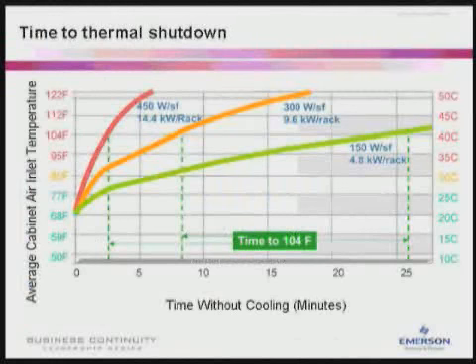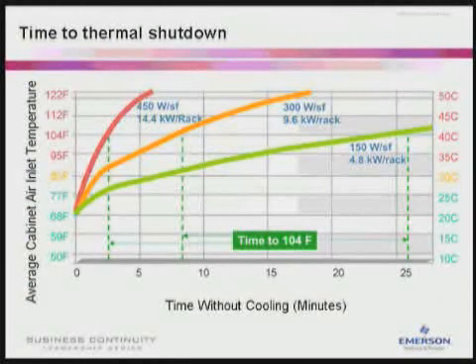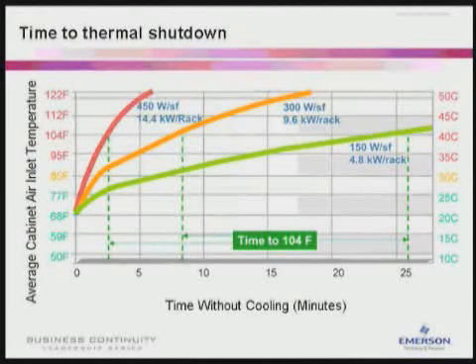Add EPO and user errors, and that percentage goes to more than half of all load loss. Slide. Most server manufacturers say that about 40 centigrade is the maximum heat their equipment can stand. After that, shutdown is not your only problem. You're also looking at component degradation.